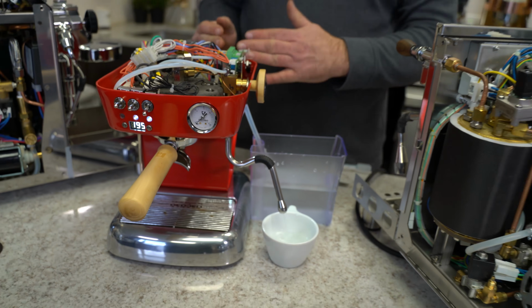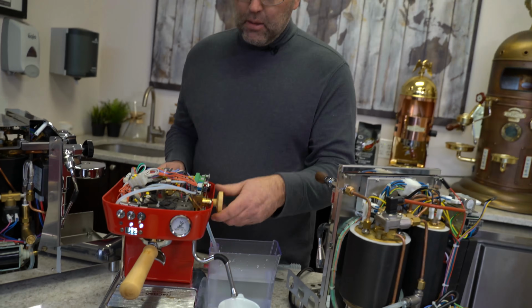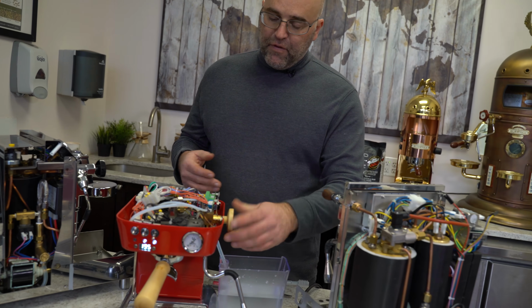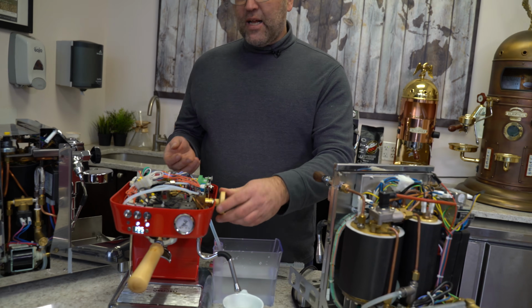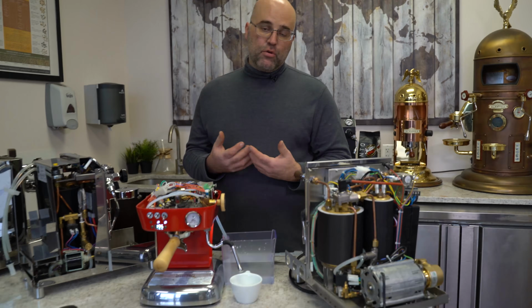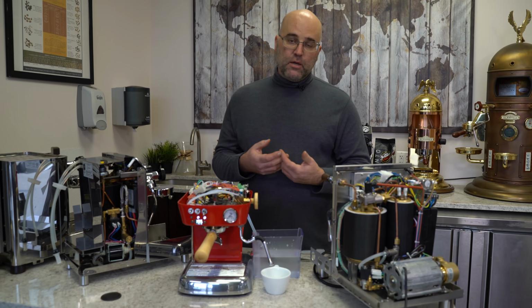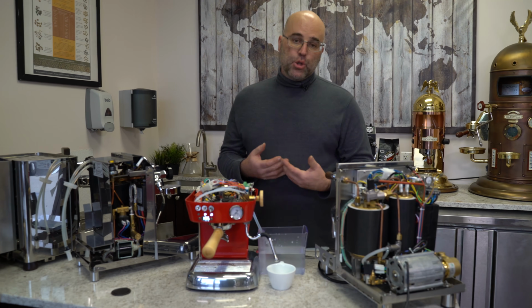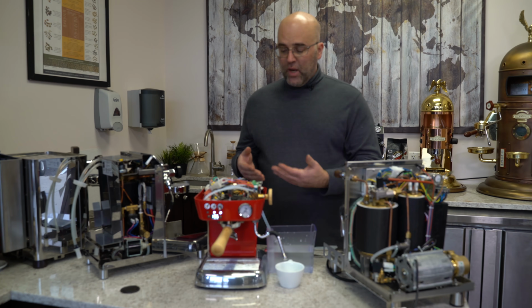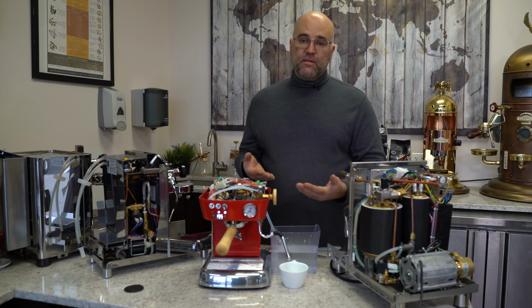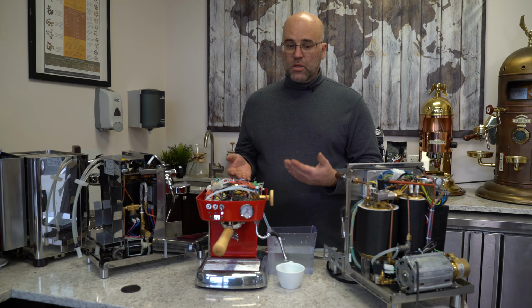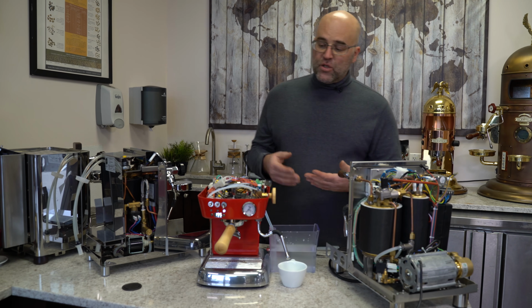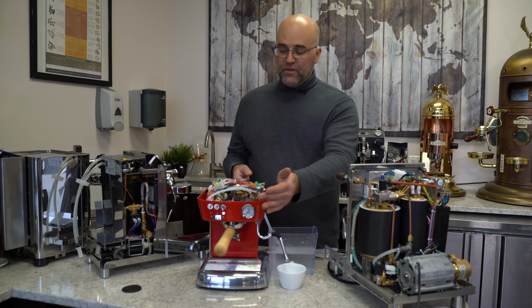Again, this can happen just from an air pocket, and the air pocket occurs either from when the machine is drained before shipping, after testing from the factory or from us here at First Line, and we have to drain it because in freezing weather the water will freeze inside the pump and damage it, or one of the hoses.